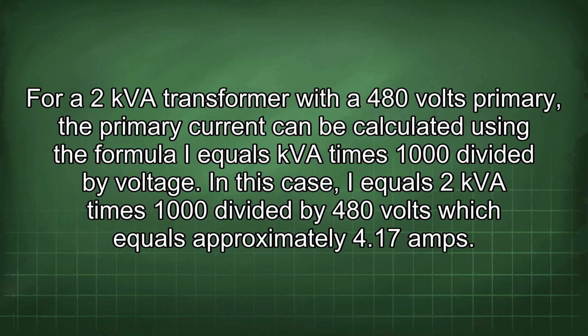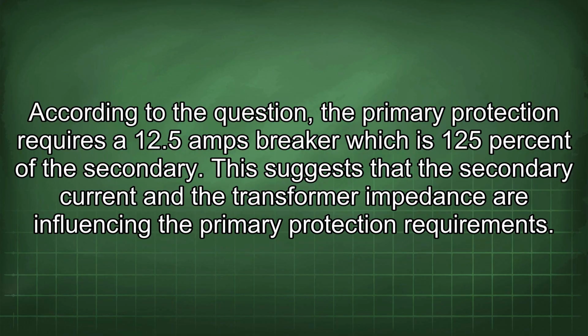For a 2 kVA transformer with a 480 volts primary, the primary current can be calculated using the formula I equals kVA times 1000 divided by voltage. In this case, I equals 2 kVA times 1000 divided by 480 volts, which equals approximately 4.17 amps. According to the question, the primary protection requires a 12.5 amps breaker, which is 125% of the secondary. This suggests that the secondary current and the transformer impedance are influencing the primary protection requirements.